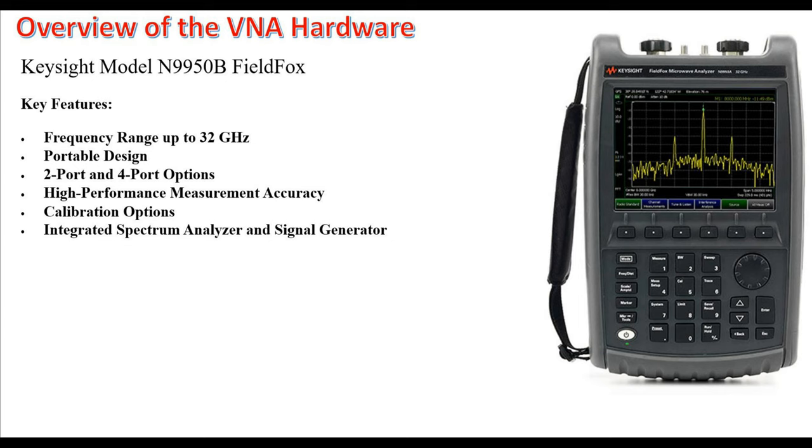Moreover, this VNA also supports various calibration methods, including short, open, load, through, and electronic calibration, which we'll go over in detail during the calibration portion of this video. This versatility ensures we get optimal accuracy across a wide range of frequencies. Another amazing feature of this VNA, beyond VNA functionality, is that it can also function as a spectrum analyzer and a signal generator, which provides additional testing capabilities in a single device.